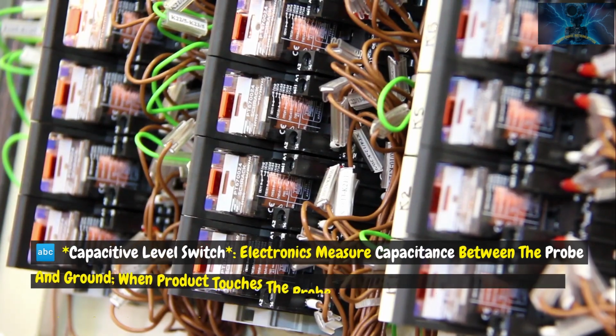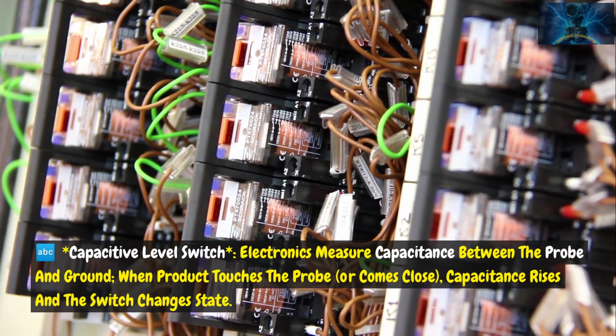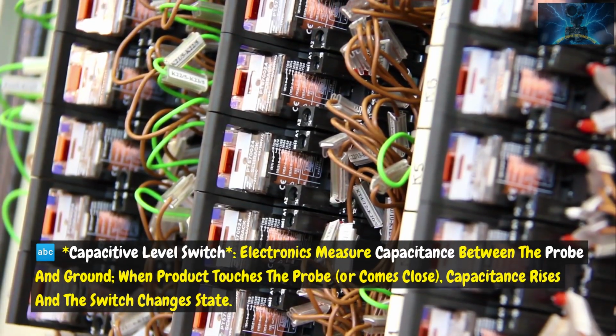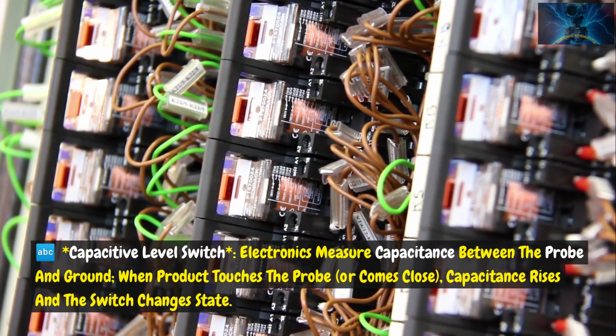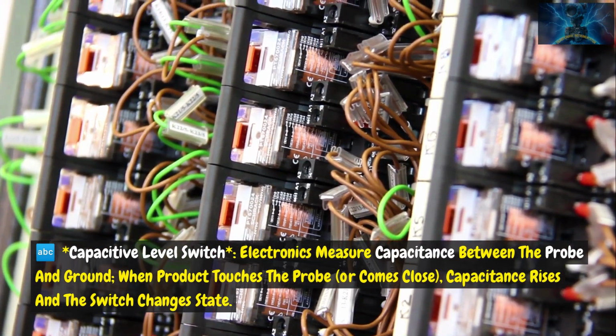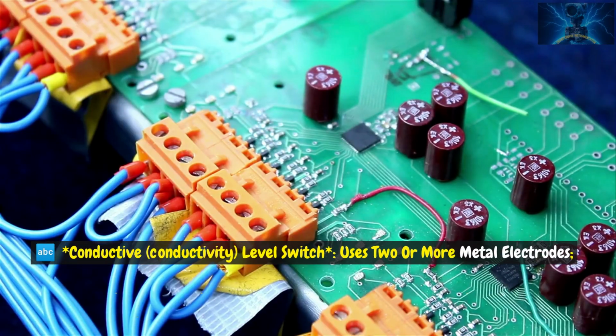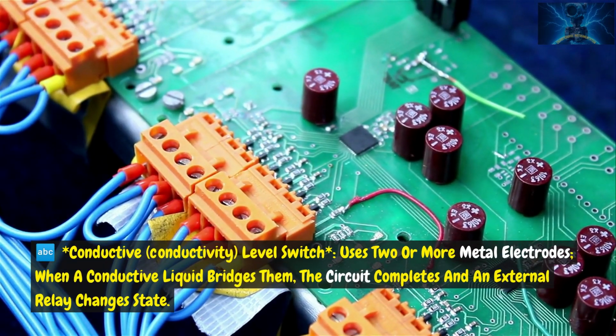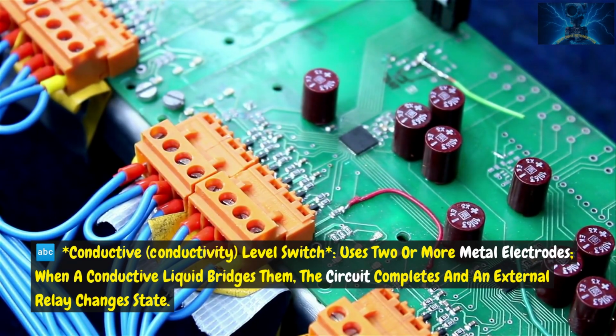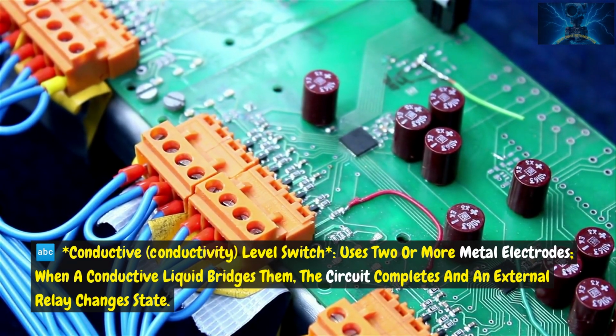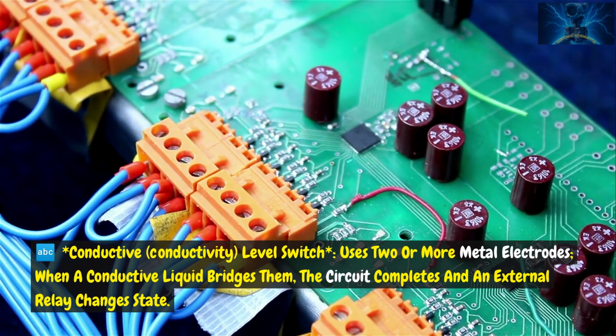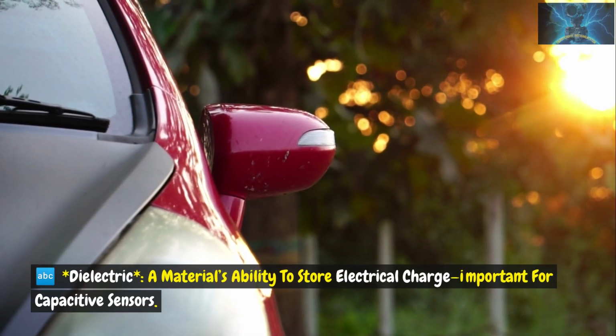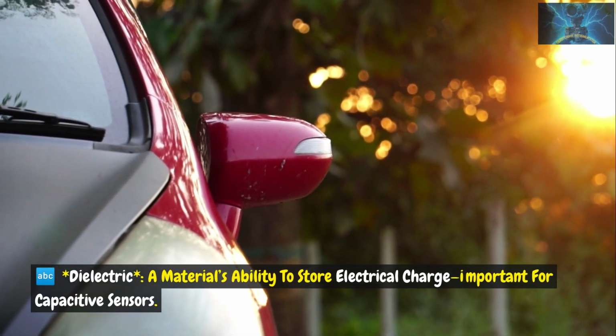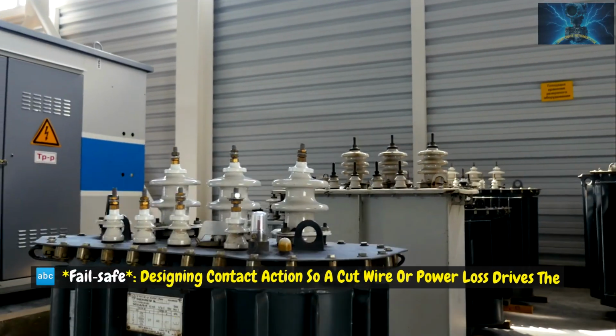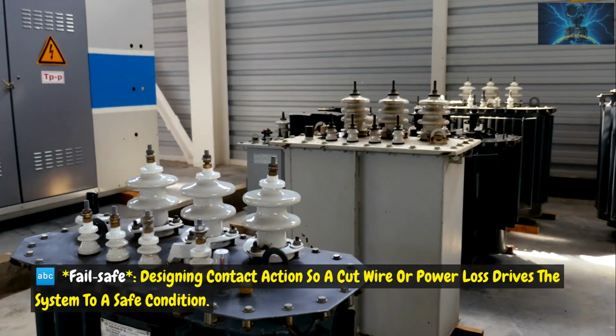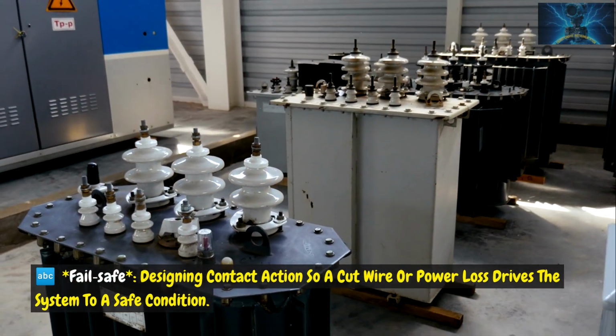Capacitive level switch: electronics measure capacitance between the probe and ground. When product touches the probe, or comes close, capacitance rises and the switch changes state. Conductive, or conductivity, level switch: uses 2 or more metal electrodes. When a conductive liquid bridges them, the circuit completes and an external relay changes state. Dielectric: a material's ability to store electrical charge, important for capacitive sensors. Fail-safe: designing contact actions so a cut wire or power loss drives the system to a safe condition.